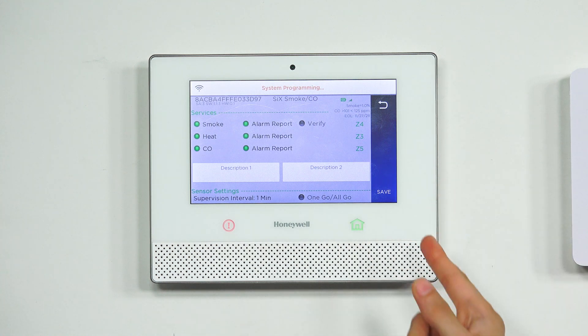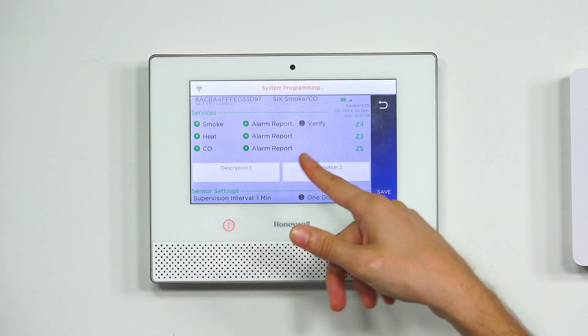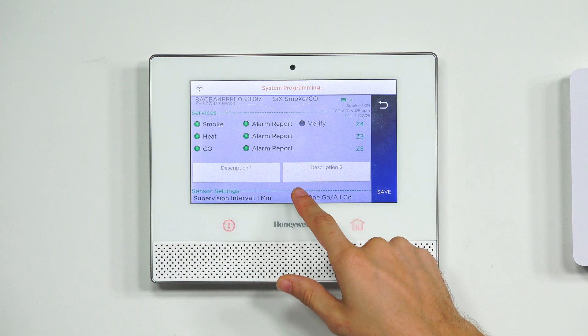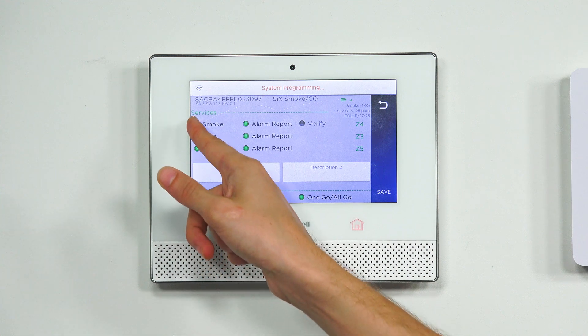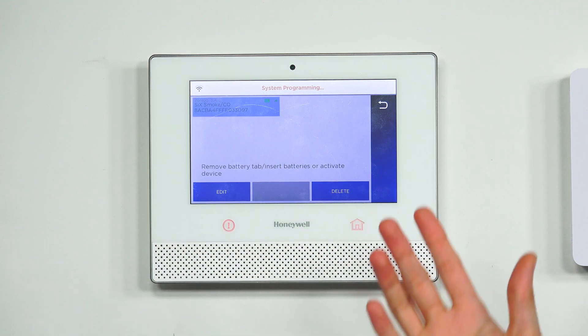Remember to press the Save button in the bottom right corner so that it saves the changes — if you don't press Save, the changes won't apply. We also have OneGo AllGo here — we want that on, so that all other SiX Combo and SiX Smoke devices on the system will activate together. We have everything set up — Smoke, Heat, CO, and OneGo AllGo — so we choose Save. And that's how you can use the SiX Combo for only smoke or only heat by turning off the other functions.